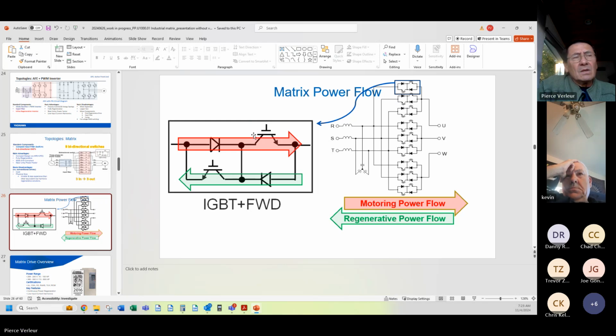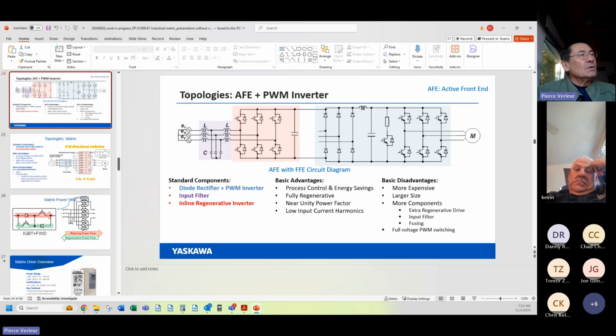Why is that important? Well, it tells you that it really is an AC to AC conversion. Number two, when we're running at full speed, we have this mode in the matrix drive called eco mode, where we do that exactly. We just turn the matrix drive into a contactor. Because why pulse to the motor if you've got 60 hertz, 460 volt power, and you want to go full speed? No, just pass that power just like you did back in the old days with a contactor. Motor's happy as a clam in mud, runs full speed, no harmonic distortion, very good efficiency. So that eco mode is possible because the AC to AC conversion is direct in the matrix drive. It is not through an intervening DC bus with a big capacitor bank.